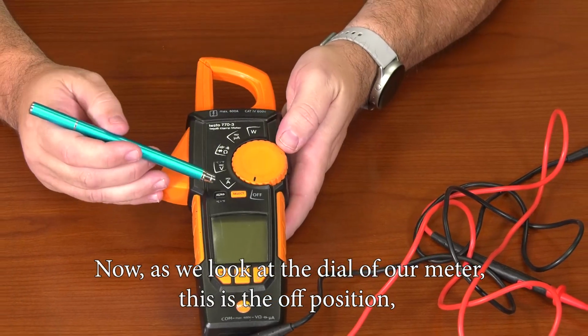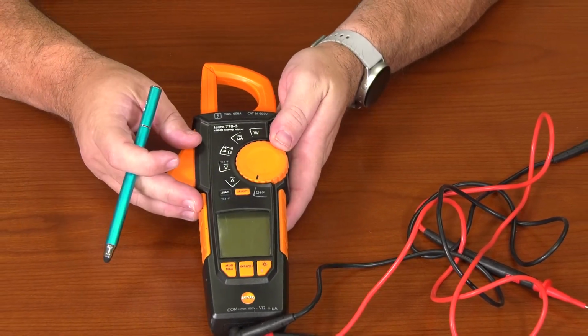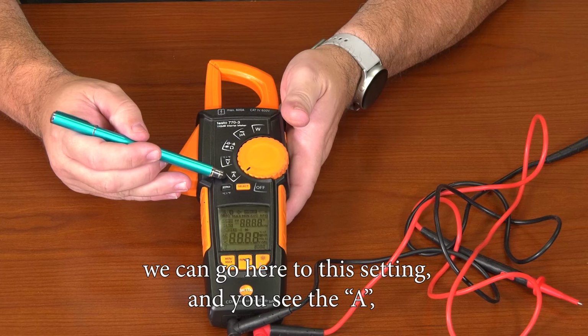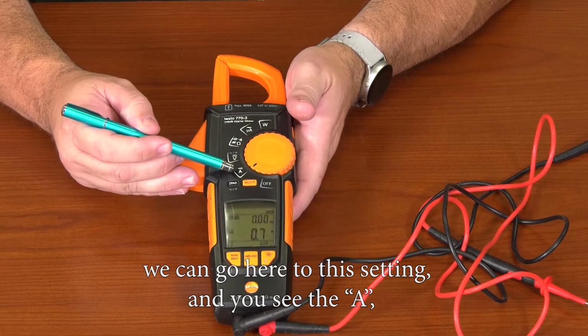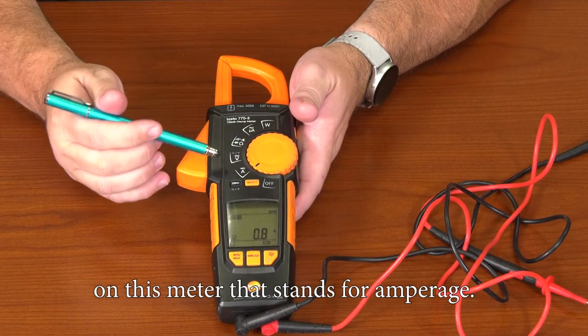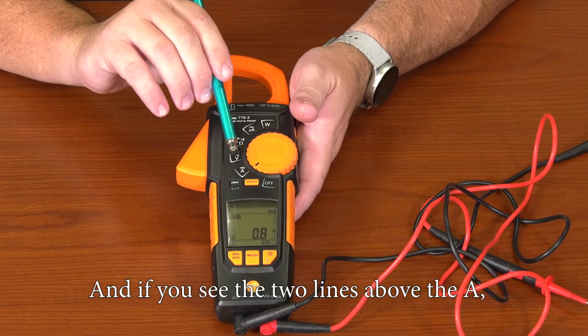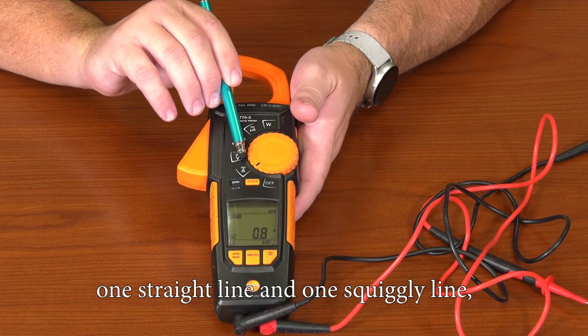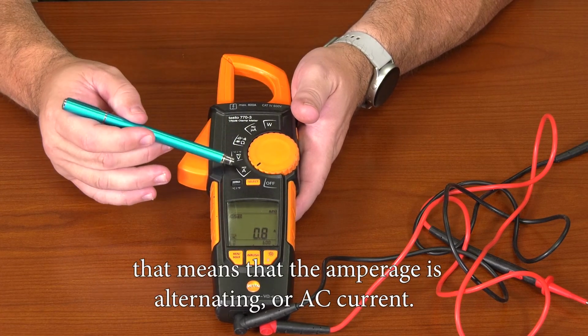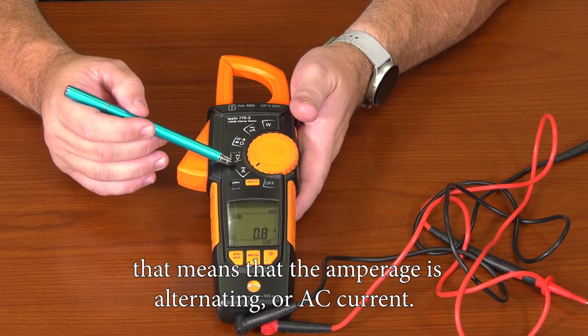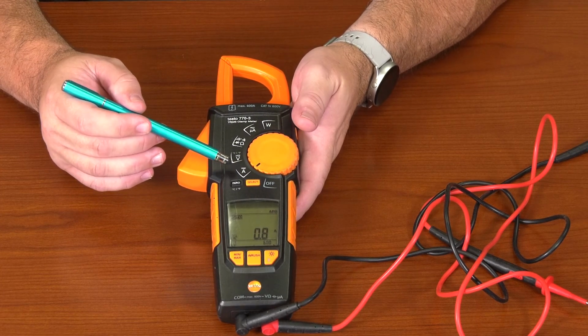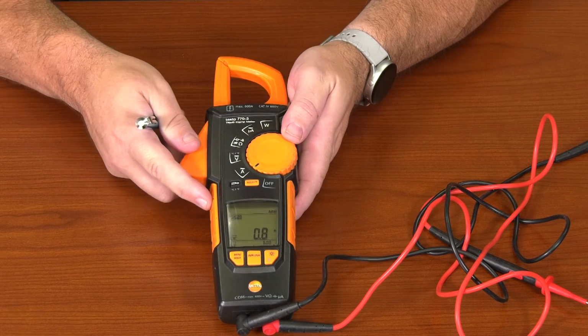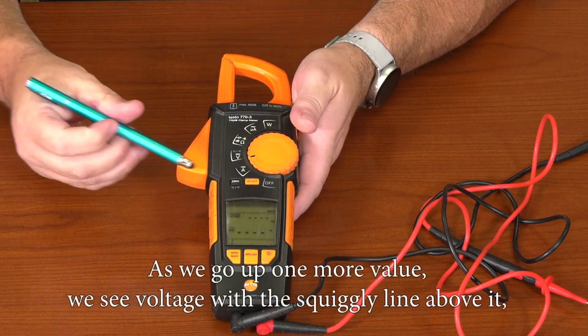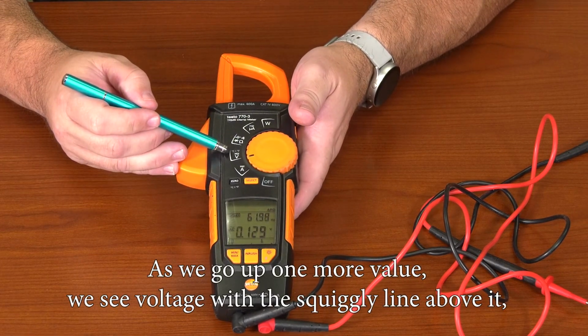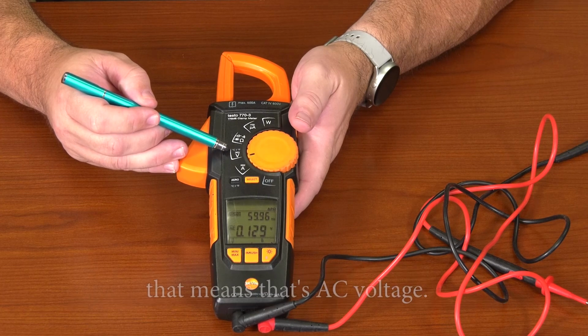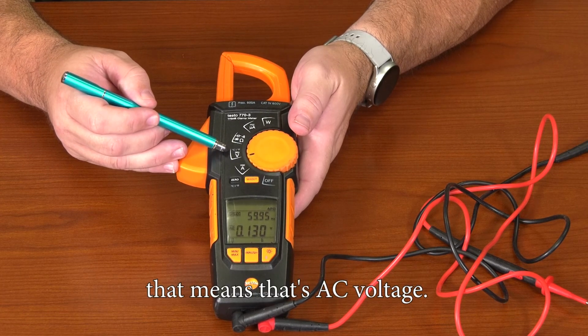Now as we look at the dial of our meter, this is the off position. We can go here to this setting and you see the A on this meter, that stands for amperage. And if you see the 2 lines above the A, one straight line and one squiggly line, that means that the amperage is alternating, or AC current. That's going to be your AC amperage. As we go up one more value, we see voltage with the squiggly line above it. That means that's AC voltage.